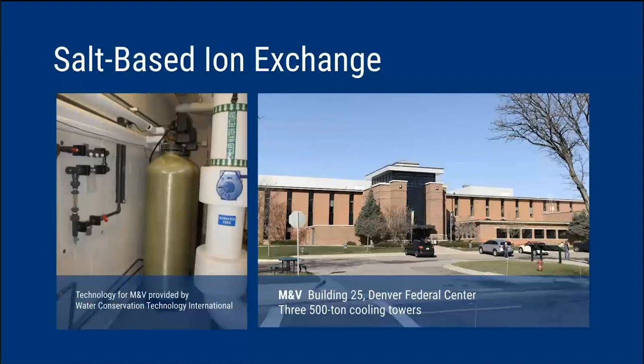So the Denver Federal Center, for example, has automated 15-minute meters on cooling tower blowdown, cooling tower makeup, on some of the chilled water plants, and also had extensive building automation system trend logs. And so we essentially were using the existing M&V infrastructure that was in place for these. So a little bit different approach, but you'll see they all performed very well, and the results are pretty crystal clear on what we were seeing here. I also have 3 different technologies to get through today, so I'm going to be going pretty quick through these just to be cognizant of everyone's time.